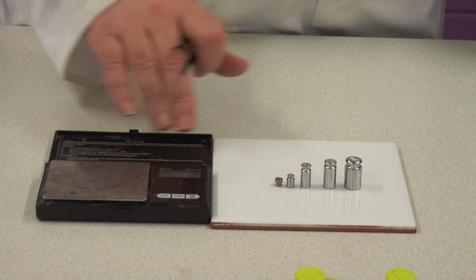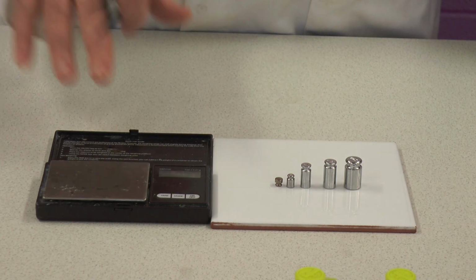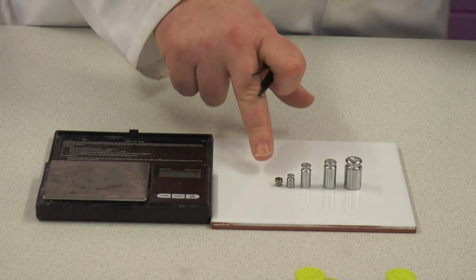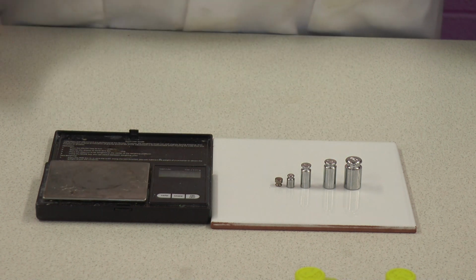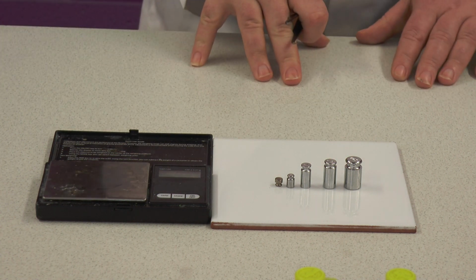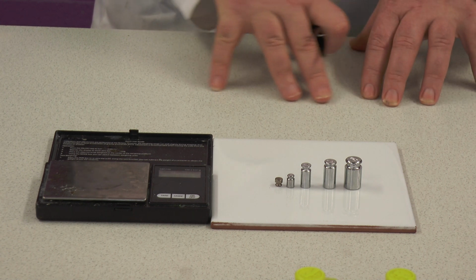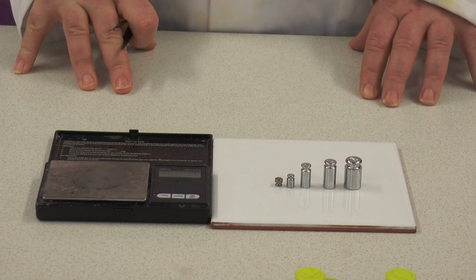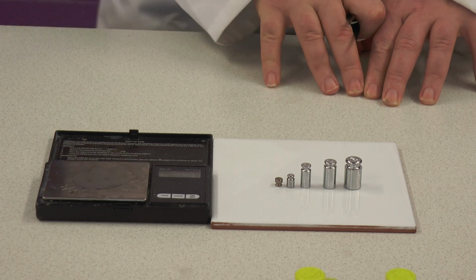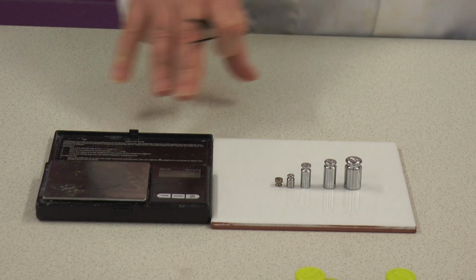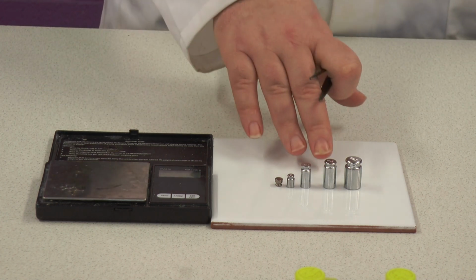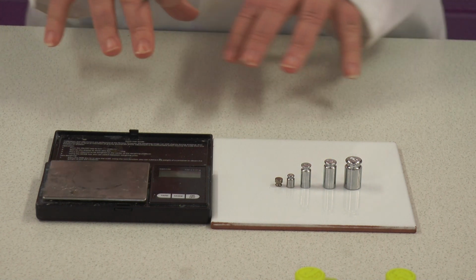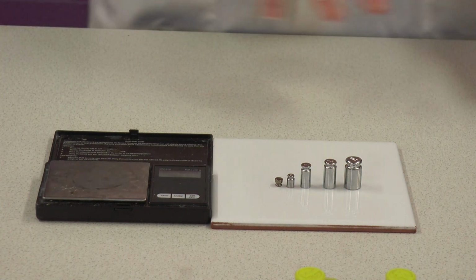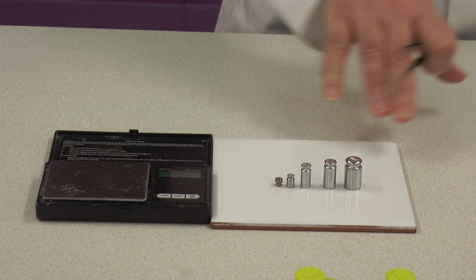What's also important to remember, and this is why we were talking about linear, is that this calibration, because we're using 1 to 20, would only work for things within 0 to 20 grams. We couldn't put something at 50 grams on this, having used this calibration method, and then take a reading off it, because we haven't calibrated it beyond 20 grams.